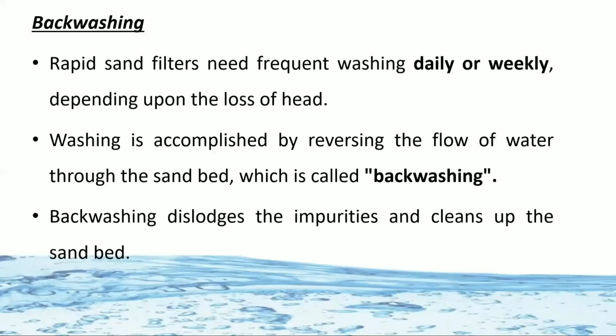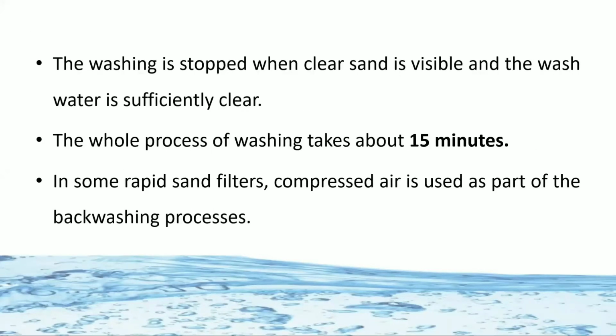The word suggests backwashing means reversing the flow of water. So it should be washed daily or weekly. For washing, the flow of water is reversed through the sand bed, which dislodges the impurities and cleans up the sand bed. The washing is stopped when clear sand is visible and the wash water is sufficiently clear. This process of washing takes about 15 minutes. Here, sometimes compressed air is used as a part of the backwashing process.